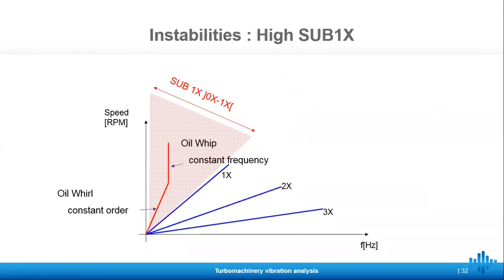Going back to the high sub-1x: in red is the area where we compute the energy for the sub-1x, and this red line clearly shows the two stages mentioned before. As soon as the oil whirl at the low order crosses the natural frequency of the shaft, we will get the oil whip. So we have two phenomena — one linked to the order and the other linked to the frequency. This is why the sub-1x is relevant: we don't need to track one frequency and one order, we only need to look at the trend.